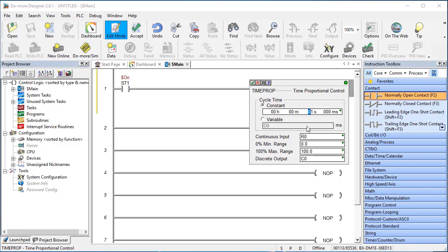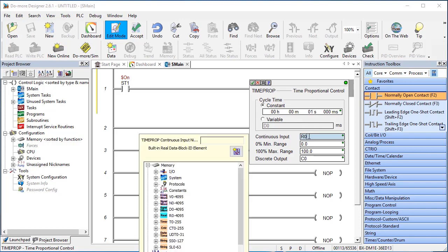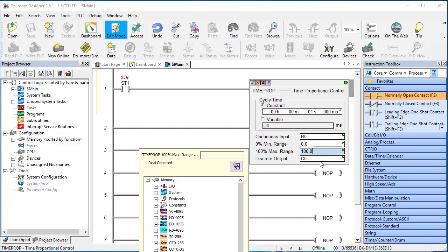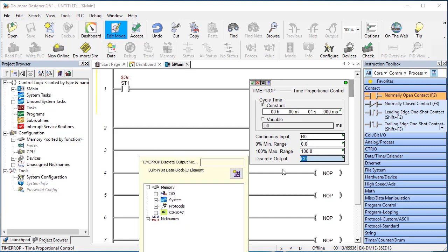The cycle time just needs to be something faster than the response time of the heater, which is several seconds. So I chose one second to keep things simple. We'll control the pulse width with R0 and it will go from 0 to 100%, and we'll use this to drive output Y0.